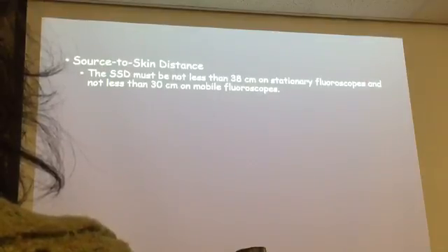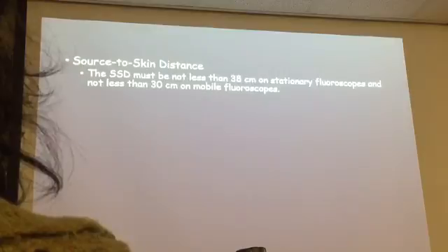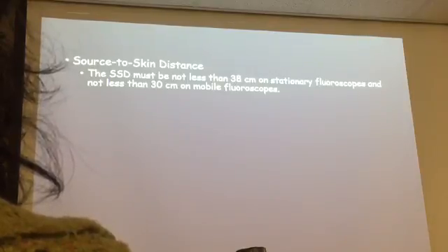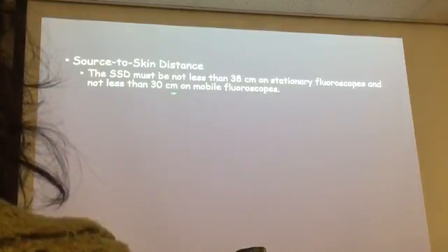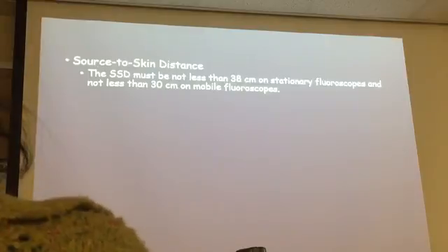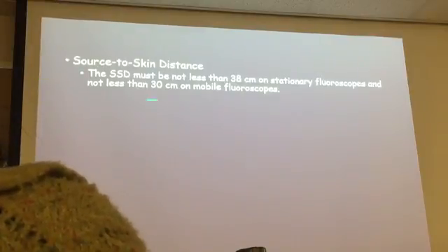You can tell the doctor he can take the cone off, but it has to be initiated by the doctor. A lot of times they just take it off because the doctors don't understand why that cone is there to begin with. But it is required, so it will not allow the doctor or the technologist to get any closer than 30 centimeters. Is that clear?